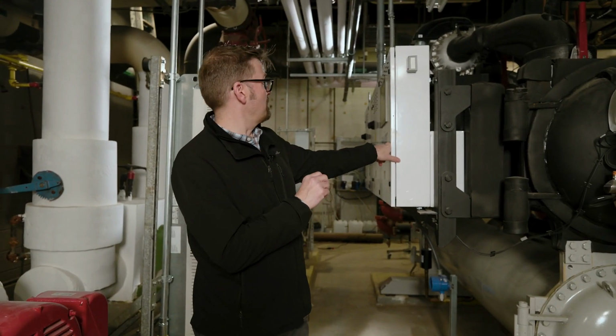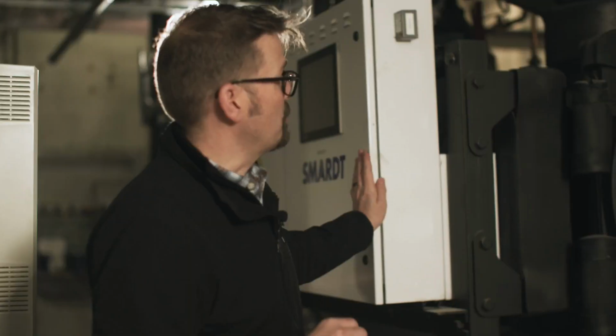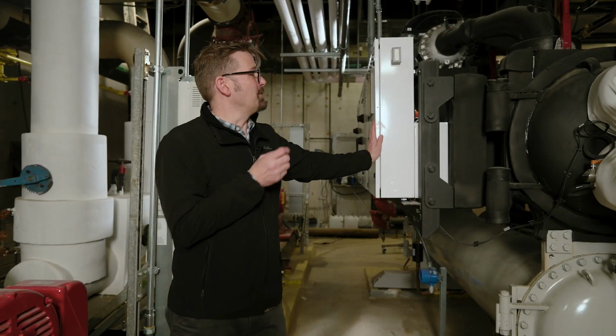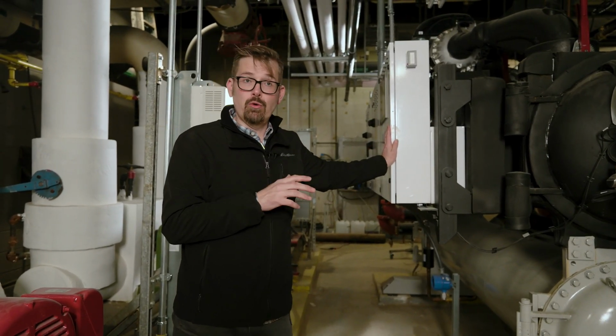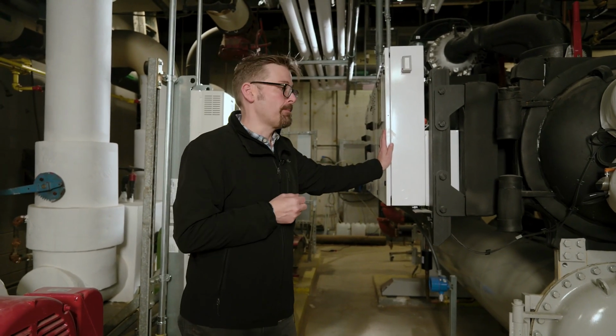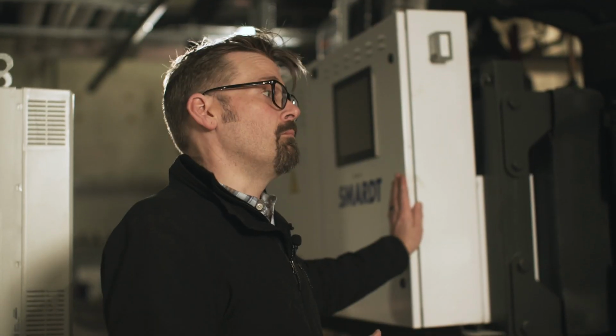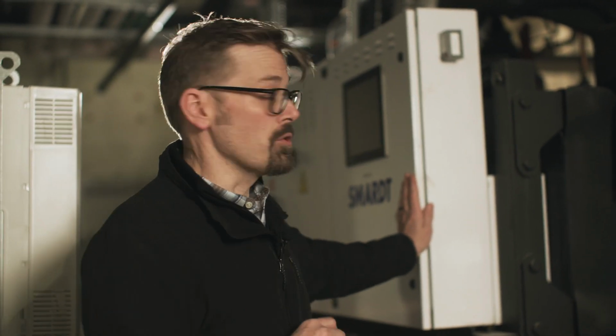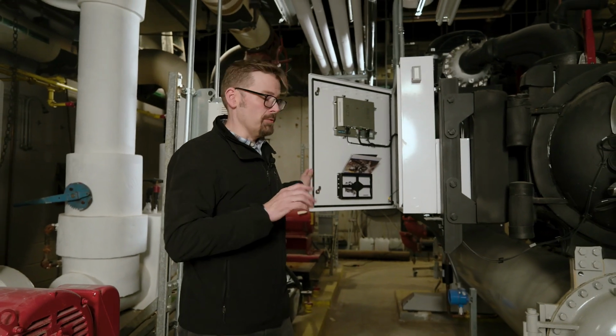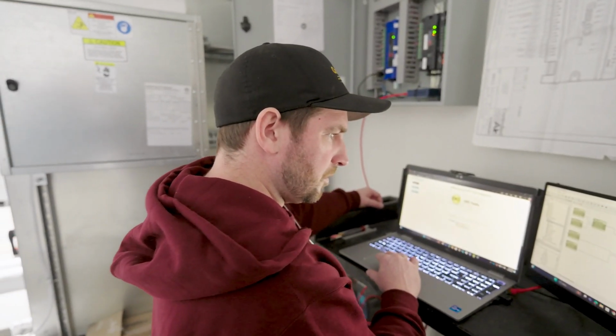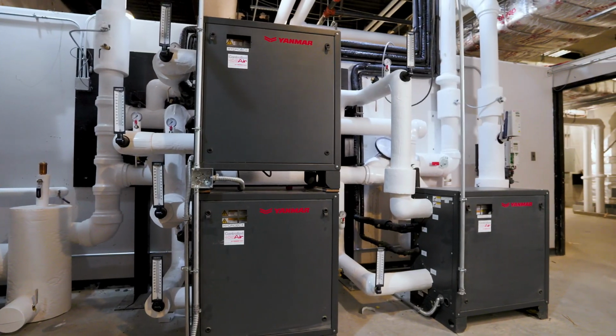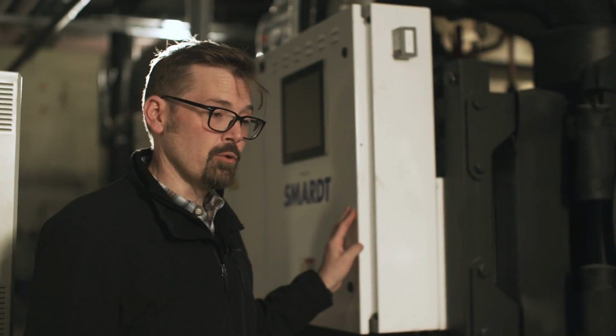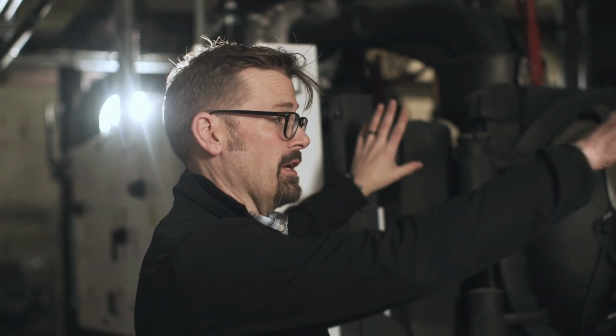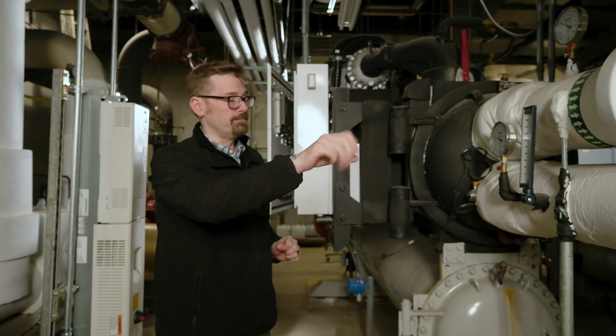What's nice about the Smardt chillers is that they have Turbocor compressors, which are a magnetic bearing compressor instead of your standard oiled metal-on-metal bearings. And you get more efficiency and longevity out of those compressors than you would out of a standard scroll compressor. And your noise levels are much lower than your standard scroll compressor or screw compressor. Smardt chillers allow us to communicate from our control center to their control center and operate these in the most cost-effective way possible for the building and for the tenants. These 2 chillers support and serve the chilled water coils within the main air handler that supplies air to the whole building. They're efficient and they're quiet.